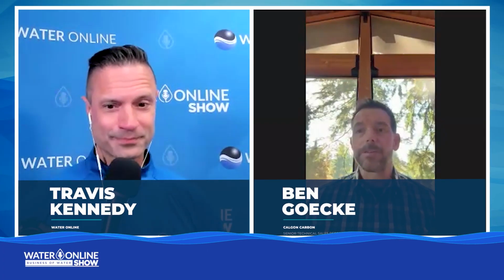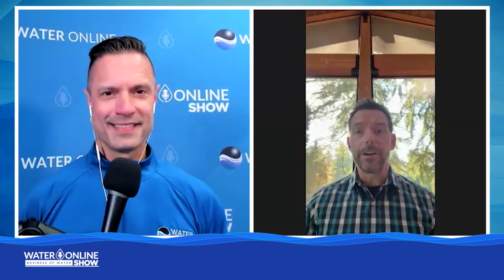And I've certainly heard that claim before. I think if you really think about it, it tends to be the opposite, and I'll tell you why. Yeah. That claim tends to focus on the difficulty of lining the internals of these vessels, right? The cone has more internals, so more care is needed to properly line it. But as long as your welds are smooth and you're following the lining manufacturer's application instructions, you're really not going to see an issue. If you want to talk about serviceability, the main thing that is going to affect the utility year over year over year is changing out that media.